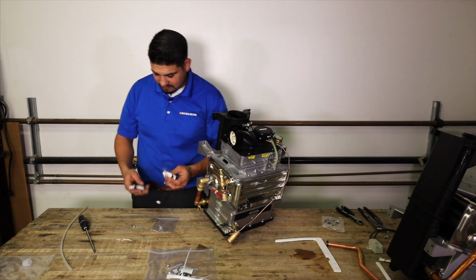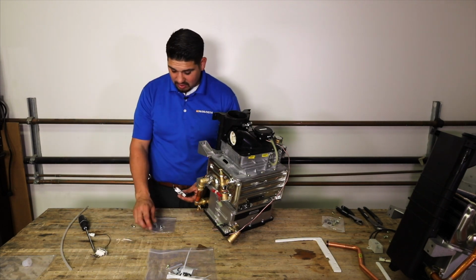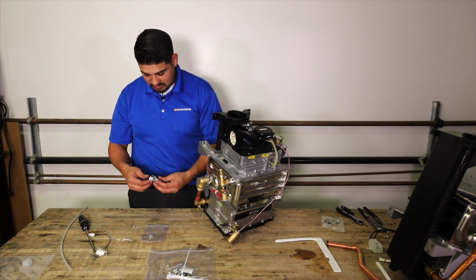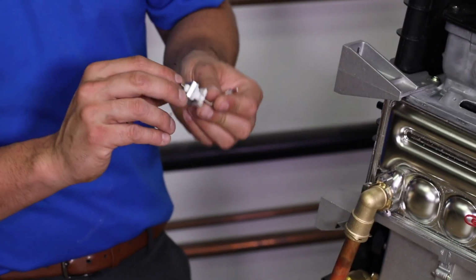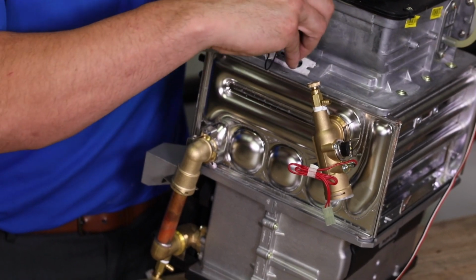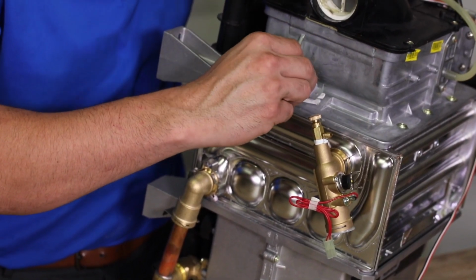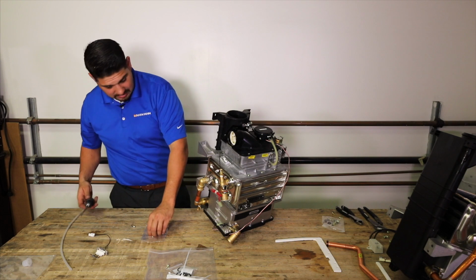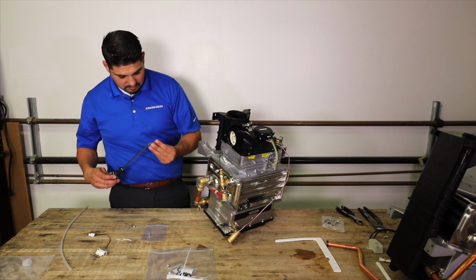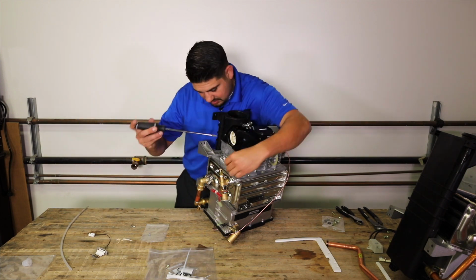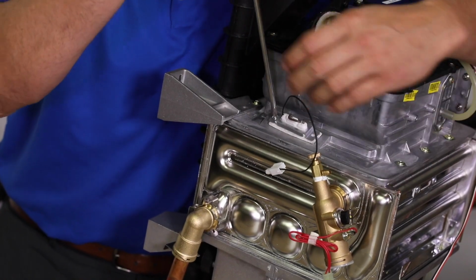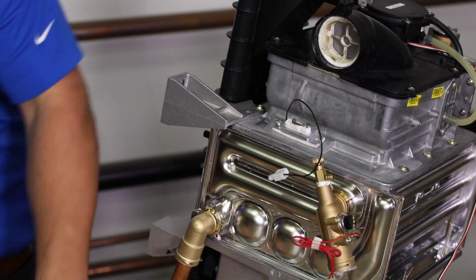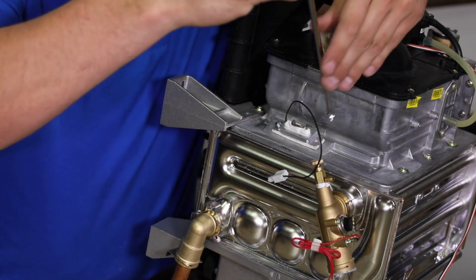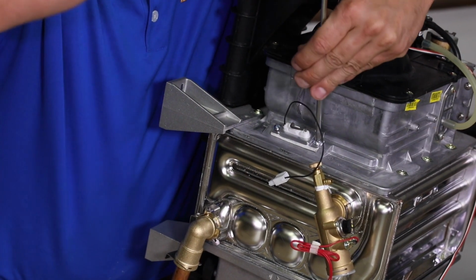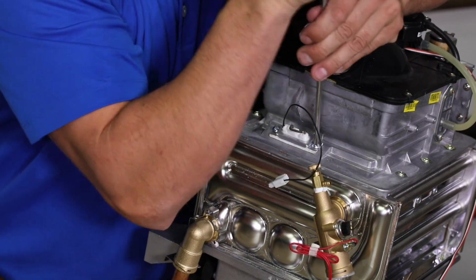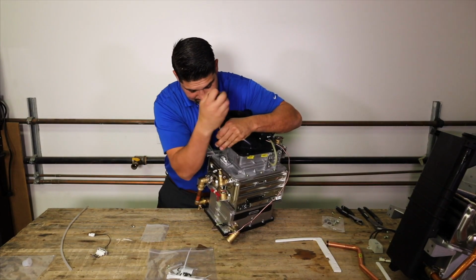This is your old flame rod. We're going to set that aside. New flame rod already comes with new hardware, new seals. Just try to be as careful with it as I can, it's pretty delicate, kind of fragile. New flame rod's in. Just align these screws. The second one aligned. Let's tighten this up.